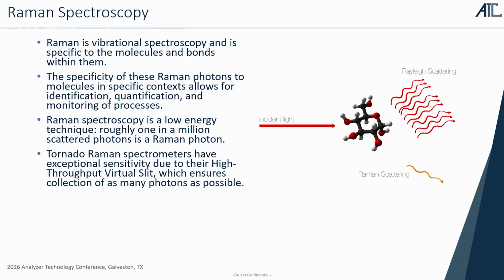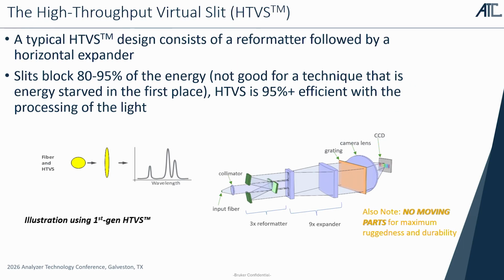So essentially, Tornado spectrometers, and Tornado is a company that Bruker bought a couple of years back, have a very unique way of gaining sensitivity along with the selectivity that is so commonplace in Raman products. They do that by using a high throughput virtual slit. Instead of blocking 90% of the light with a mask slit to gain resolution, they will cut up the light that's coming off of a fiber, which is just a round circle of light. That's these return photons, 1 in a million, right? So you've got to catch them all. It's kind of like Pokemon. The idea is that we want as much energy efficiency with Raman as we can get. But the trade-off is oftentimes resolution, right?